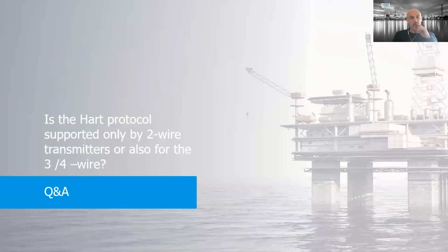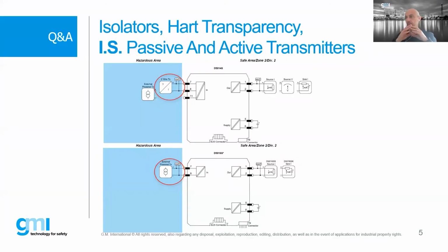That is another question, and here we have an example where you have isolators. In the first picture, you see the 2-wire. The 2-wire means passive transmitters that are powered through the modules, in this case, and the HART is retransmitted on the output. You see also on the output side that the HART is over there. There are other modules. But in this case, this module from us is not externally powered, the HART is not retransmitted. So that is well specified in the manual, basically.